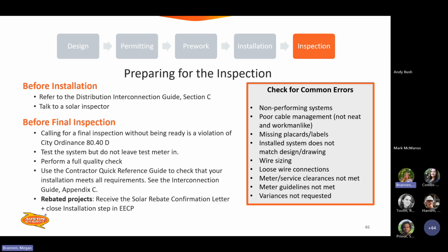I'm just going to note a few of these common errors. So non-performing systems, poor cable management. This one gets called out pretty often. If it's not neat and workmanlike, we'll call you out for poor cable management and make sure that that gets fixed prior to passing that final inspection. Just missing placards and labels, missing address labels. Installed system does not match design or drawing. Again, because you can upload throughout the permit lifecycle, you should be able to have the most up-to-date as-built system design on the permit itself. Additional errors could be wire sizing, loose wire connections, and the inspectors will check for these things as well.